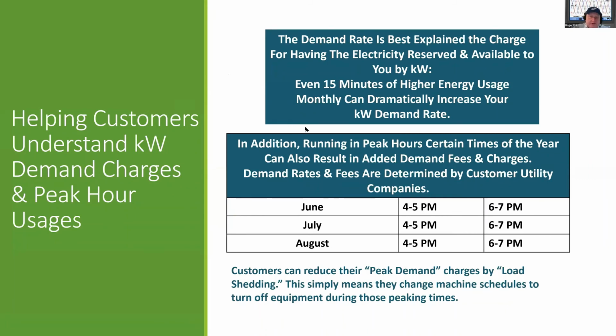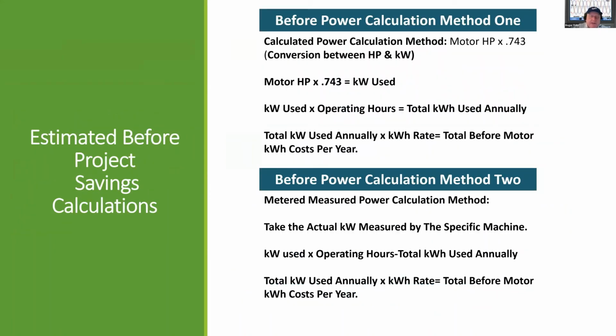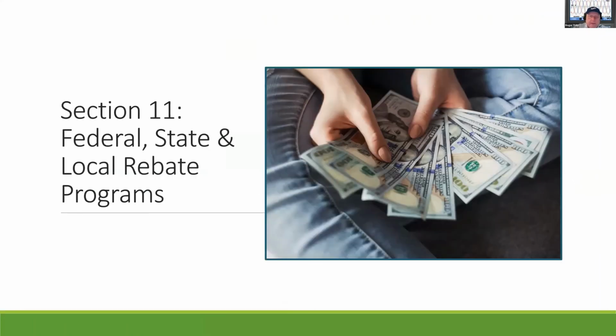The other thing that we go into is demand charges on your power bill: the difference between KVA and KW demand, and time of day. Typically in the United States, demand is charged after a 15-minute period of a given load for that 30-day period. You get stuck with that demand, whether it be high, low, or during the different peak periods, and then they keep track of it. There's also the proper understanding of before and after calculations on power use. There are also a lot of federal and state rebate programs out there.